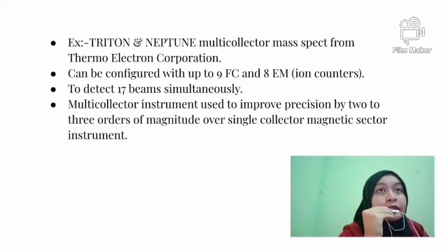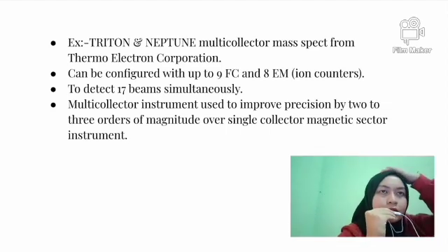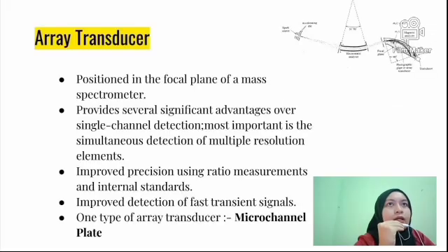The function is to detect 17 beams simultaneously. Multi-collector instruments are used to improve precision by 2 to 3 orders of magnitude over single collector magnetic sector instruments.